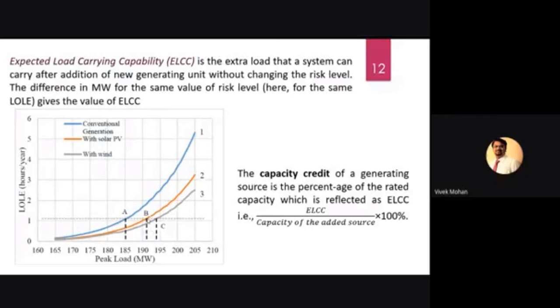But at a particular point, both the blue curve and the orange curve have the same LOLE. For conventional generation, this same-LOLE point is at 185 megawatts. When you expanded the capacity, the same LOLE occurs at 191 or 192, a 7 megawatt difference. That means when you expanded the capacity using solar PV, at the same risk, the system can take an additional load of 6 to 7 megawatts.